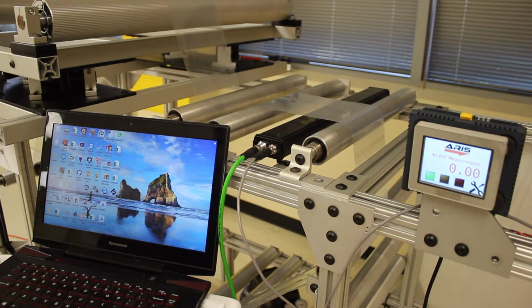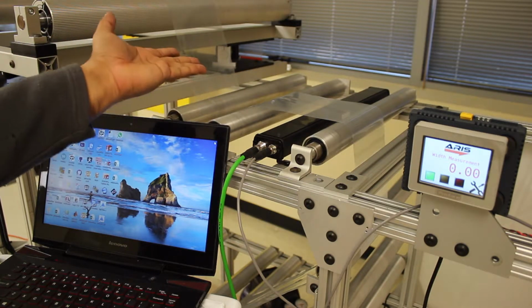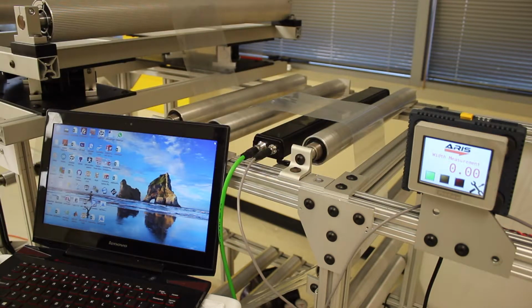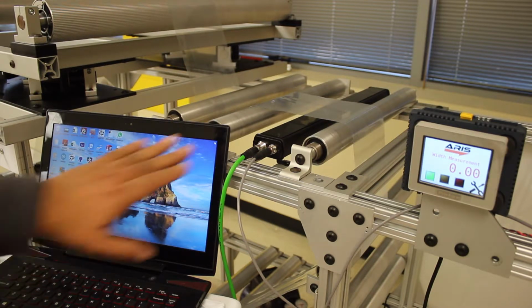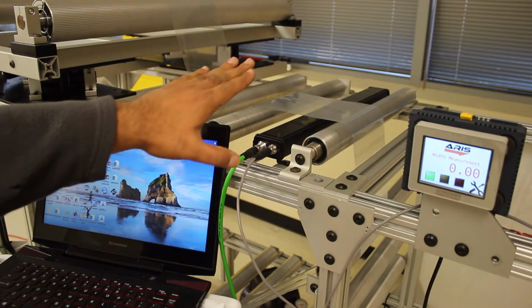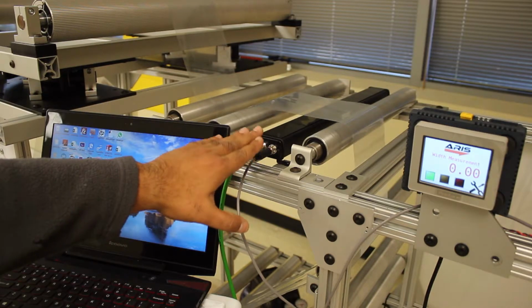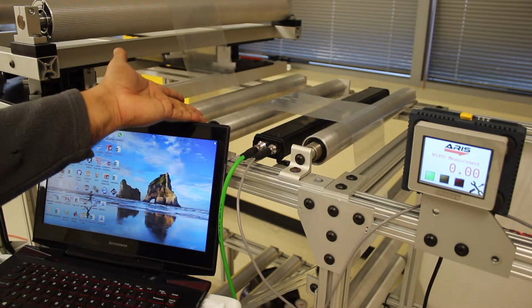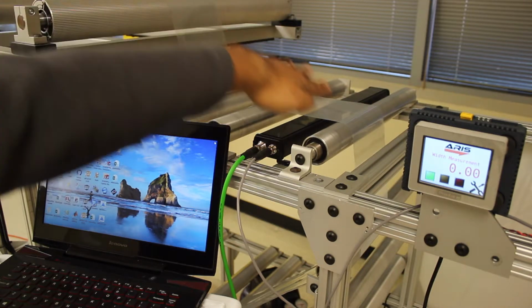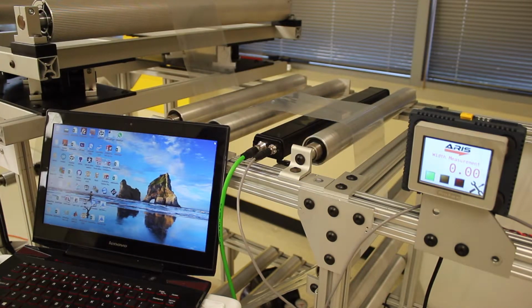There's also a way for us to get the maximum scattering out of the sensor. If we want to do that, we will raise up this roller so that the web comes at an angle. About 15 to 20 degrees is the angle that we want, and it depends upon the orientation of the sensor. So if you want to get the maximum scattering, we will raise up this roller so that the web comes this way. But those are the few things that you want to consider before installing our 440 for width measurement application.